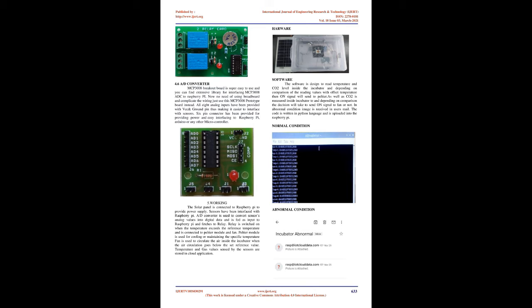CO2 sensor: a gas sensor used to detect the level of CO2 inside the incubator. It gives information about the percentage level of CO2 gas, which can be used to infer the oxygen level. As the CO2 level increases, that indicates a decrease in the oxygen level. It is specified by having a fast response, stable, long life, and simple drive circuit.